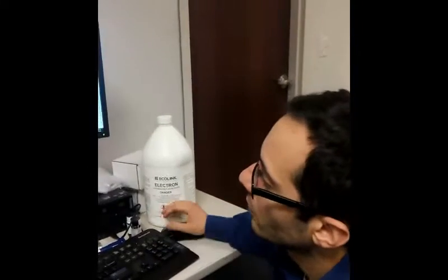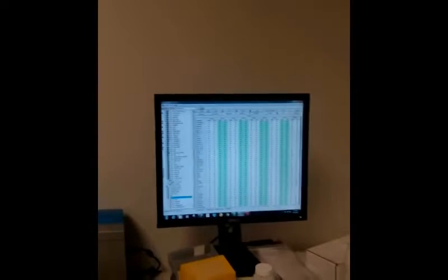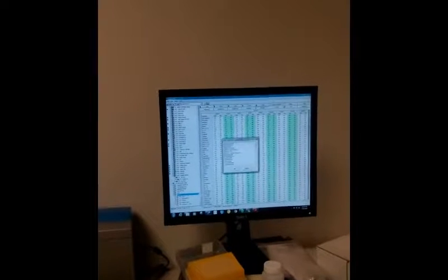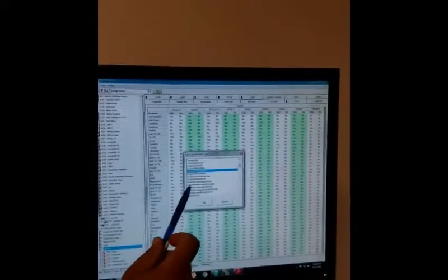That's why. So, for example, if I look at my Spectro, I don't see it right now. I don't have any other engine except for a diesel engine. So if I went to add user alarm, and with the engines, I could say I now have a normal gas engine. So maybe engine other gasoline. Reciprocating gas engine. See that? Reciprocating gasoline engine. If I go ahead and select that, it already has some typical things that you look for. But you can see here that all the alarms are baseless. So it does expect you to go ahead and put it in there.